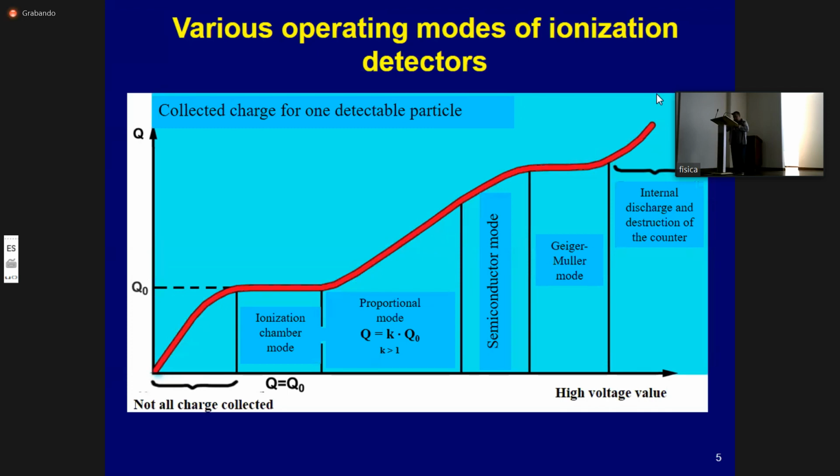This process, called impact ionization, increases the number of ion pairs formed in the gas volume and is the mechanism of gas amplification of the ionization effect of the detected radiation. Thus, the charge on the electrodes increases. Q becomes greater than Q0, and this is the mode of operation of gas discharge counters.